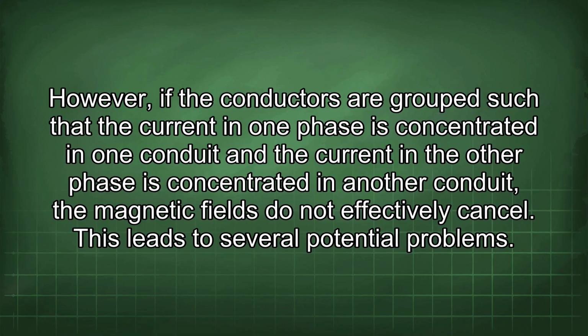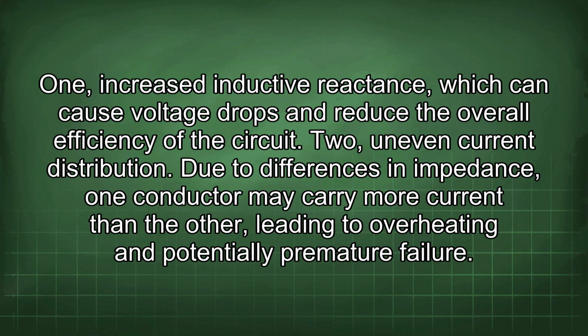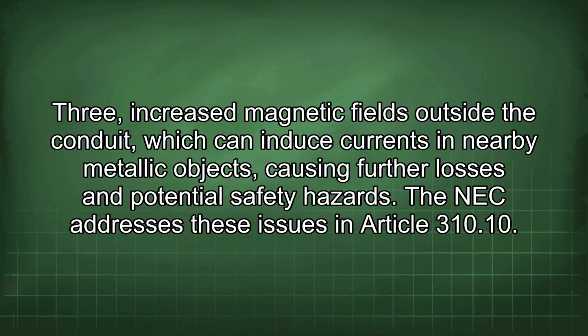This leads to several potential problems. 1. Increased inductive reactance, which can cause voltage drops and reduce the overall efficiency of the circuit. 2. Uneven current distribution. Due to differences in impedance, one conductor may carry more current than the other, leading to overheating and potentially premature failure. 3. Increased magnetic fields outside the conduit, which can induce currents in nearby metallic objects, causing further losses and potential safety hazards. The NEC addresses these issues in Article 310.10.